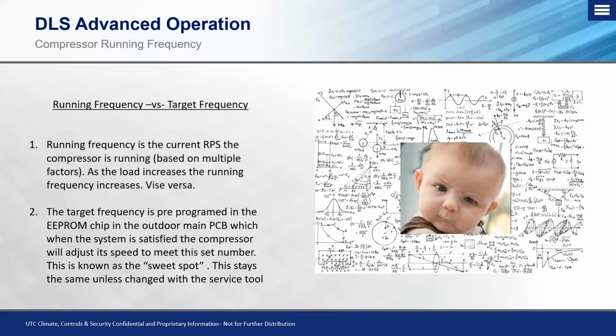Okay, and a lot of times when I start talking about the algorithms, everyone's head seems to spin. So we need to look at this from a basic standpoint. We're not talking about how to write algorithms or understand algorithms. What we know as service technicians is we know that we can have voltage in, voltage out. We also need to have an understanding of what that board is accepting as far as information and what response it's going to give based on the information that's received. We as service technicians can check that and verify that, and with an understanding of how that algorithm or control process or set of rules is configured, we can essentially assume what that process is going to be once the information is received and what command we're going to get out.